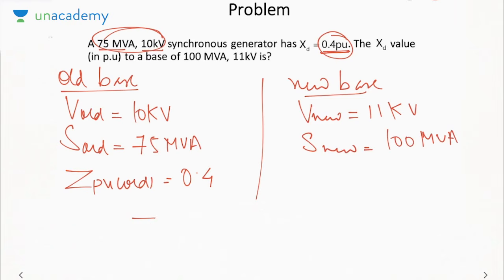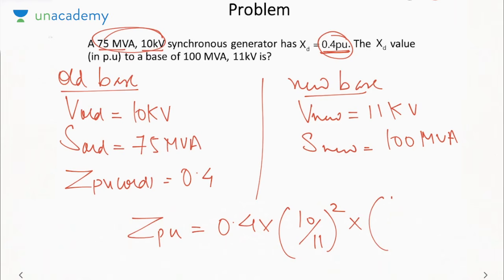So we know ZPU new is equal to ZPU old into V old by V new square into S new by S old. New is the base that you want to map to. Old is the base you want to map from. So this comes out to be how much if we calculate? It is equal to 0.44 pu. Okay, so that is how we convert the base, or we change the base of any impedance.